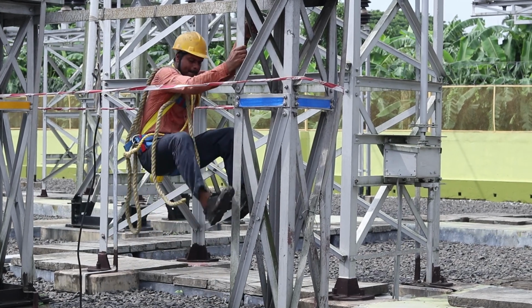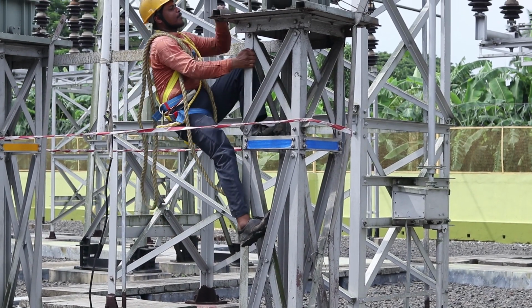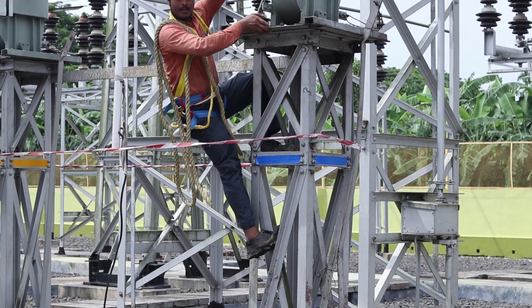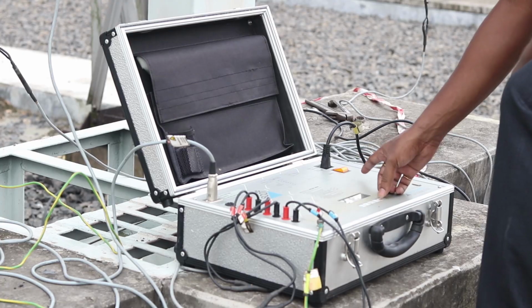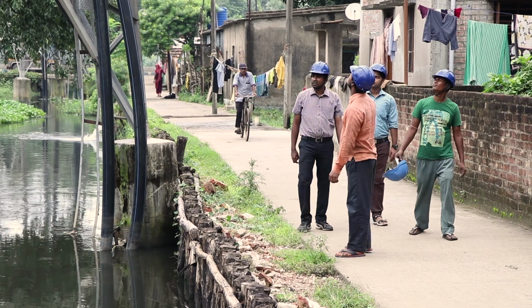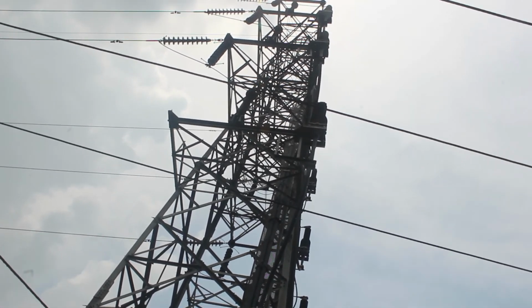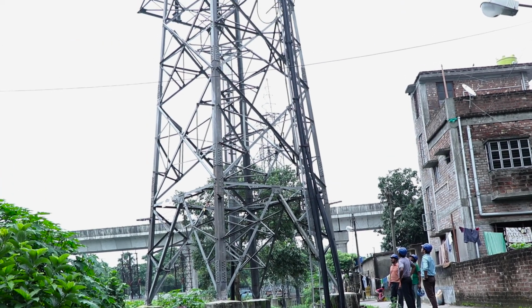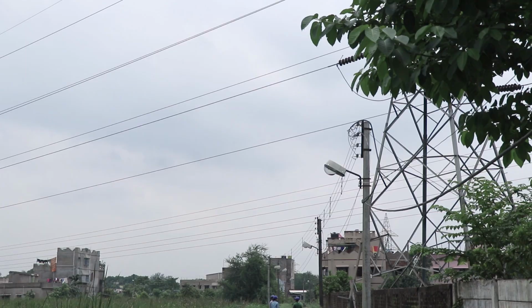I am working at Behala substation as operating personnel for the last 5 years. We perform all types of switching operation, inspection, fault detection. During work, we minutely follow all safety procedures to avoid accidents. Repair and maintenance of every equipment of the substation and transmission line is performed as per schedule. Testing and checking of equipment is done at regular intervals. Monthly line patrolling, road clearance, and line maintenance work is performed to ensure uninterrupted power supply.